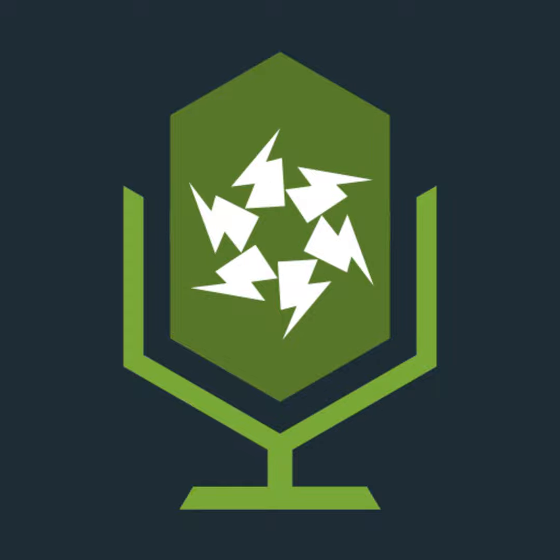Then you have an IT system, and probably the most interesting drawing is figure 16A5, which shows you a TN-CS system with 3 SPDs, and it shows you where they should be laid out. And if you look at it carefully, you can see that the SPDs are 4, 7 and 8.